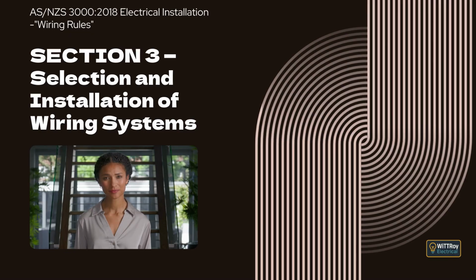This clause explains that permanent signs must be provided to show where an underground cable enters or leaves a building, unless the entry point is obvious. It also explains that the route of underground cables must be recorded on a plan so the location can be identified in the future. This plan must be kept at the switchboard where the circuit originates. Marking is not required for underground wiring installed entirely within the confines of a building.